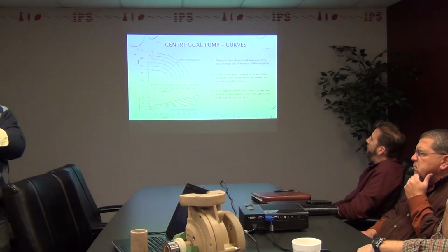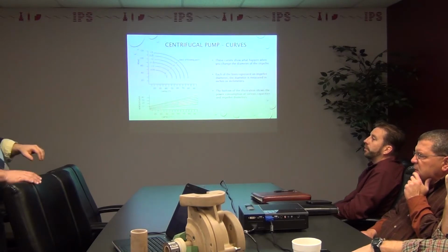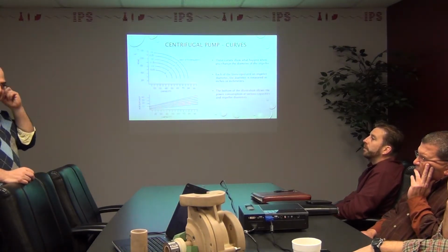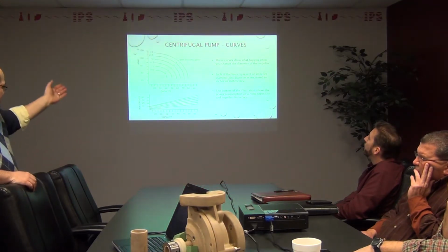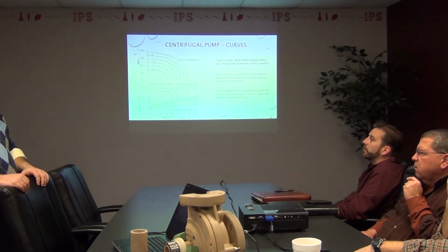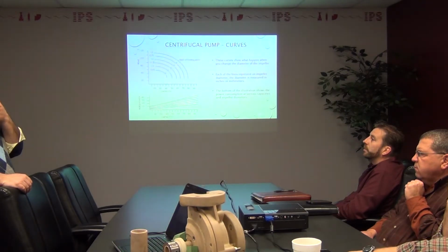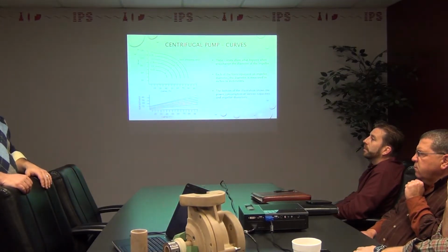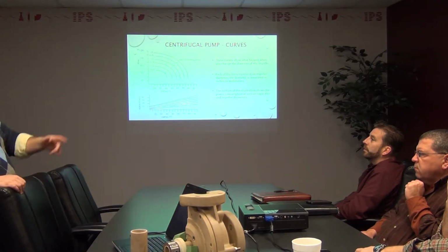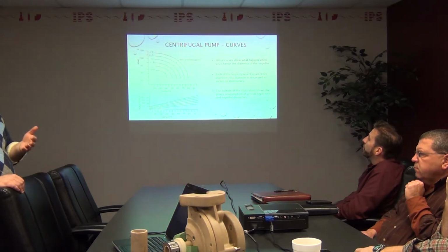So to get back to the little story, we were at an account, and the guy purchased a pump, and the application was probably right around 30 gallons at 15. We get there, and the motor's tripping out, and something's wrong. Looking at it, I noticed it was a 7.5 or 10 horsepower motor, and I'm like, boy, this doesn't look good for this loop, right? I'm like, get me the curves.